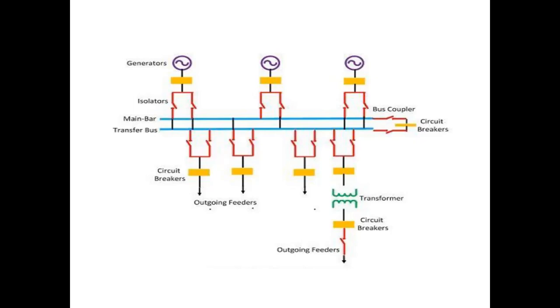In this alternative double bus system, every feeder is directly connected to a second bus called the transfer bus. Advantages include low initial and maintenance cost, and any breaker can be taken out for service while continuity of power supply is maintained by bypassing through the bus coupler. Disadvantages include that an extra breaker is required for the bus and isolator switching is somewhat complicated during breaker maintenance.